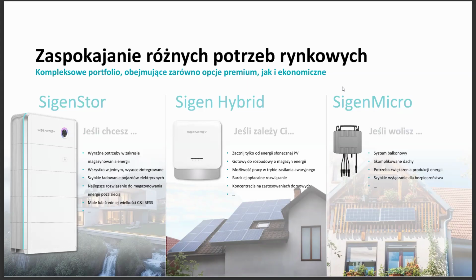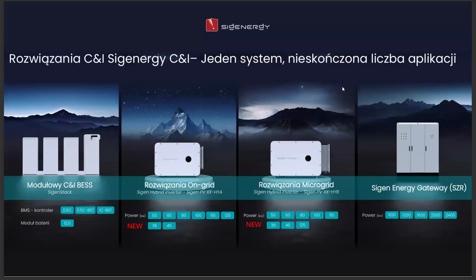What does this mean in practice for you, as designers, installers, and integrators? With this architecture, we can configure a commercial storage system from 48 kilowatt-hours up to 253 kilowatt-hours on a single inverter. This provides exceptional flexibility, from small production facilities, through office buildings and hotels, to more energy-intensive commercial sites. And I want to emphasize this point, we are talking about one specific inverter, which is critical for cost, installation simplicity, and future expansion. Inverter range tailored to real commercial needs.